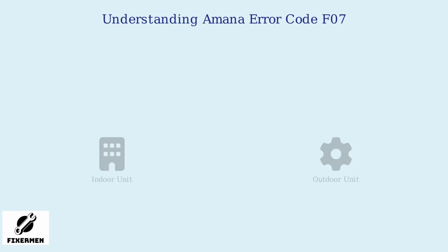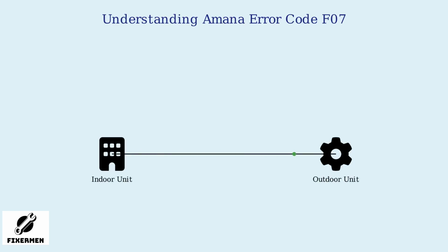Amana's F07 error signifies an outdoor unit communication timeout. This means the indoor control board isn't receiving signals from the outdoor unit, which is the condenser, within the expected time frame. The F07 error code appears when communication fails between these two units. Specifically, the timeout occurs if signals aren't received within 2 to 5 minutes.